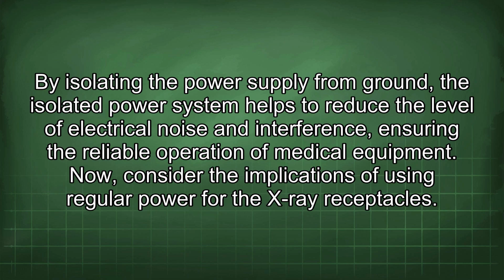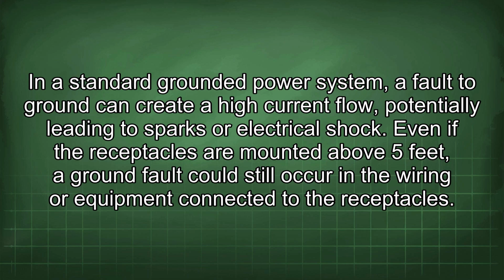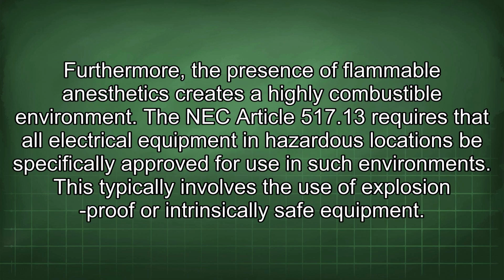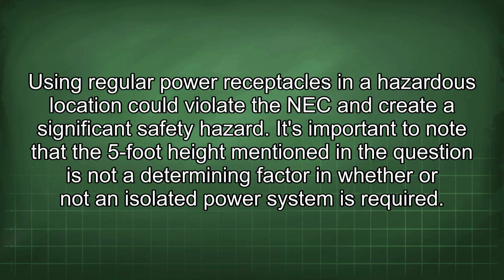Now consider the implications of using regular power for the X-ray receptacles. In a standard grounded power system, a fault to ground can create a high current flow, potentially leading to sparks or electrical shock. Even if the receptacles are mounted above 5 feet, a ground fault could still occur in the wiring or equipment connected to the receptacles. Furthermore, the presence of flammable anesthetics creates a highly combustible environment. The NEC Article 517.13 requires that all electrical equipment in hazardous locations be specifically approved for use in such environments. This typically involves the use of explosion-proof or intrinsically safe equipment. Using regular power receptacles in a hazardous location could violate the NEC and create a significant safety hazard.